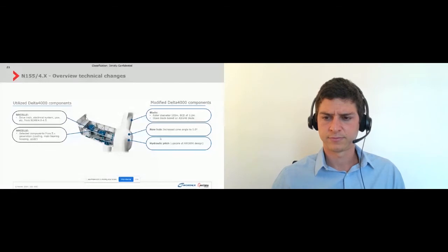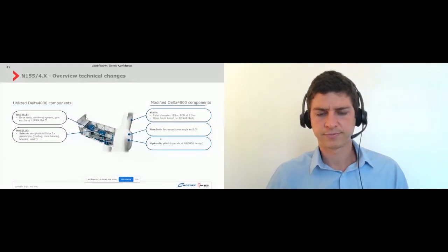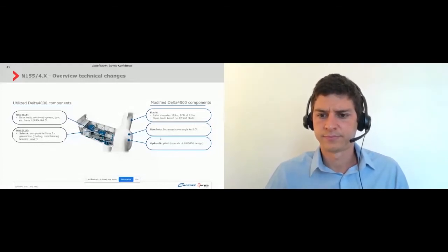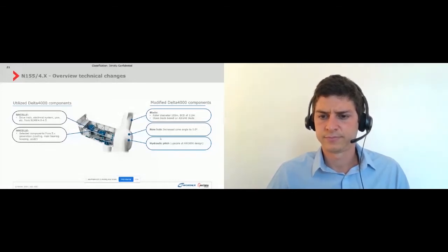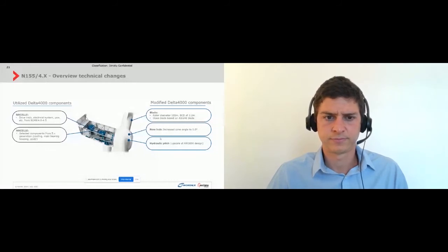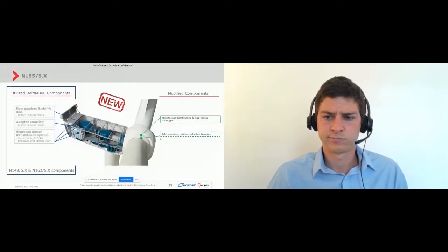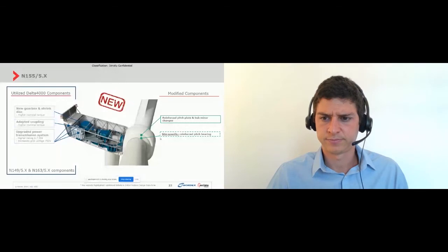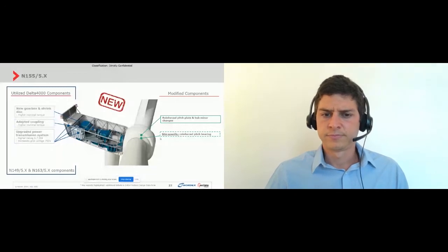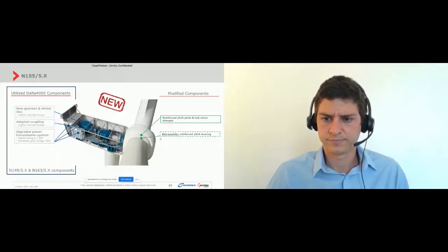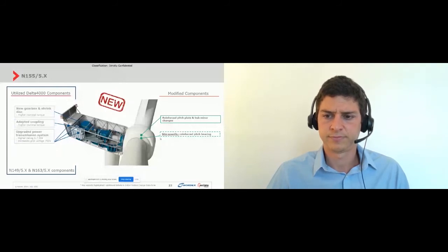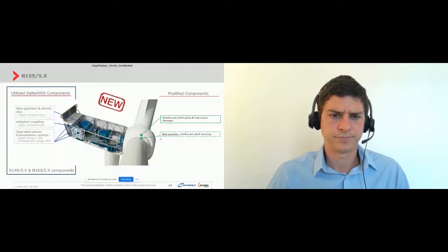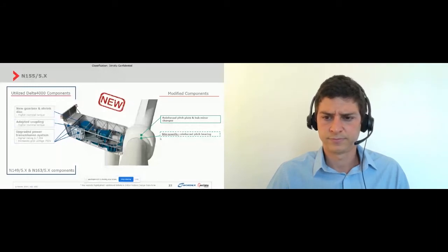And as I mentioned earlier, an electric pitch system with motors is not used, but rather a hydraulic pitch system which, again, as I mentioned earlier, is the concept that is used in the Acciona 3000 platform, original from Acciona Wind Power. And, well, a product that we launched this year is the N155 5X, which follows the same philosophy that was done with the N149, passing from 4X to 5X, practically the same updates are made of the gearbox, the coupling, the generation and electric transmission system, and which components are modified, of course, the pitch is reinforced and some changes are made in the hub, and in function of specific requirements of the site, it could count with a reinforced pitch bearing.